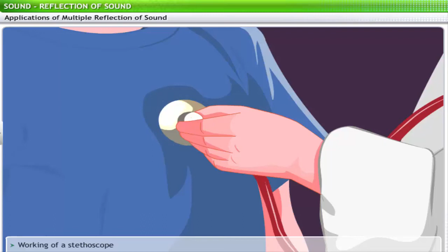A doctor using a stethoscope to give you a checkup is a very common sight. A stethoscope uses the principle of multi-reflections to help the doctor hear your heartbeat. Let's take a look at how it works. The chest piece of the stethoscope consists of a plastic disc called the diaphragm, which is placed on the patient's body. The sound of the heartbeat vibrates the disc. These vibrations produce pressure waves which travel to the listener's ears through the hollow tubes by a series of multiple reflections throughout the tubes.